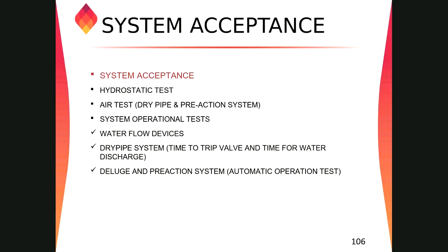Okay, so we have to check the hydrostatic test, the one we discussed, at 200 psi for 2 hours, and we have to check if there is any leakage in the system. We discussed a lot regarding that in the previous sessions. The dry test for the dry piping and pre-action system, operational test, water flow device, right?